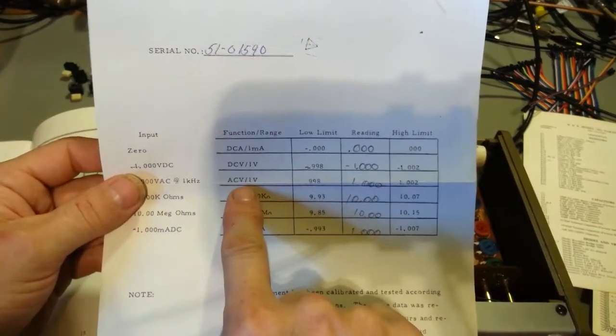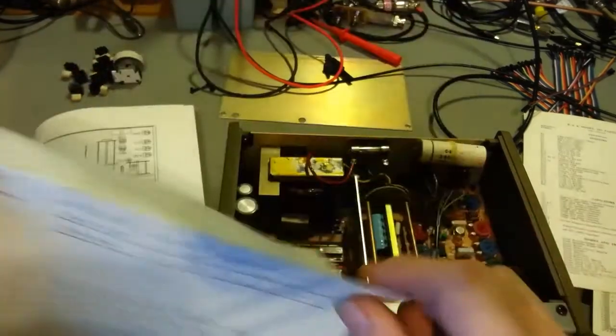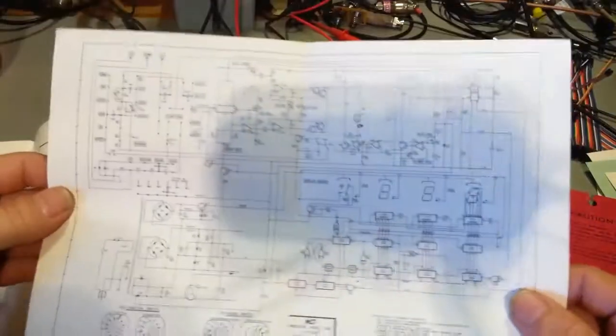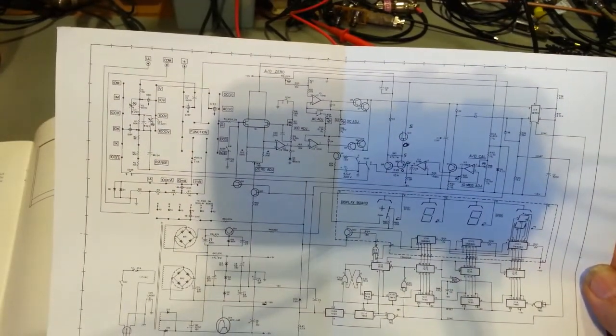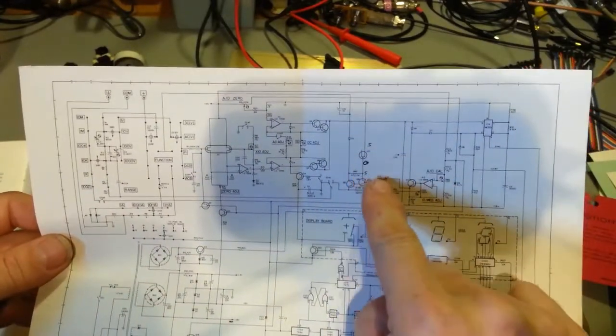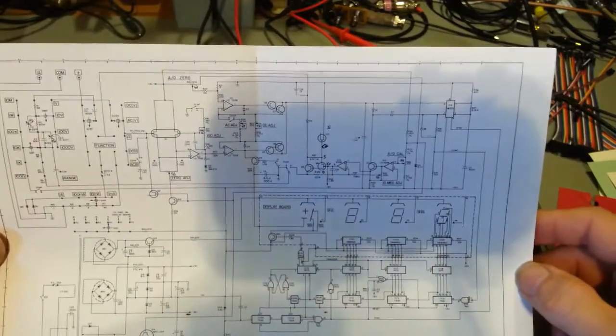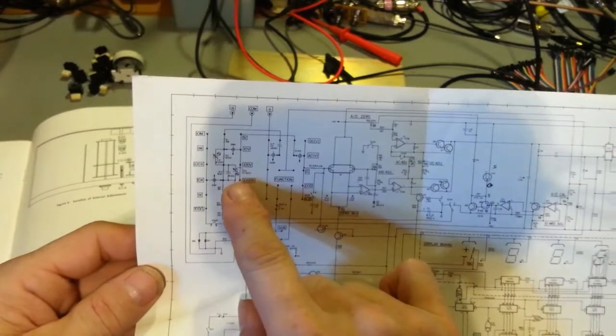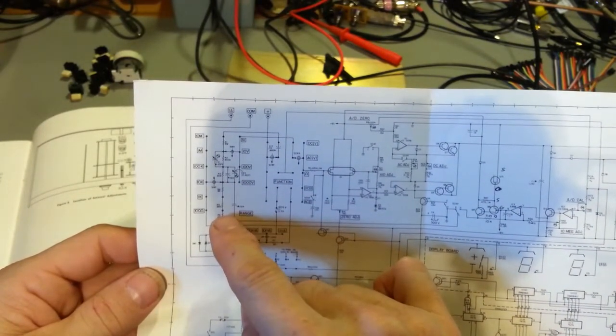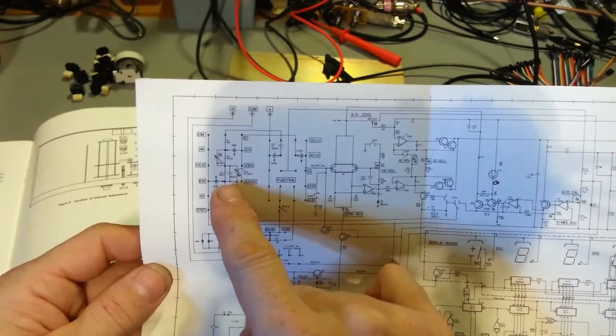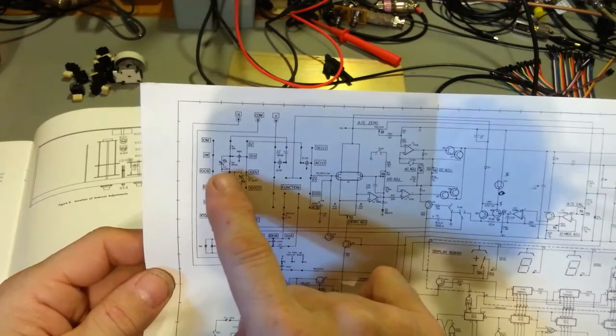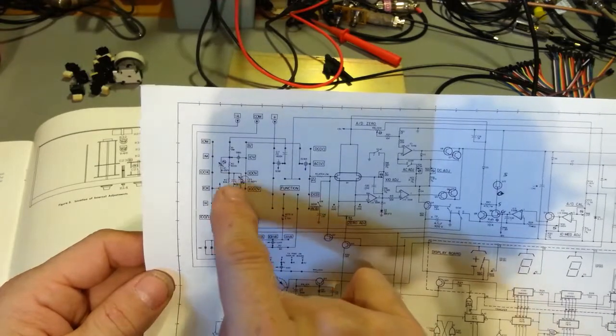Just grab this cal certificate. AC. It's only calibrated at the 1 volt range. Maybe there is a difference in this. I'm not seeing... Looks like somebody's done something to this at some point in time, because they've highlighted the gate and the sources on these FETs here. DC AC adjustment. There don't appear to be... wait a minute, right there. So they show them on the schematic. But okay, this one's in parallel with another fixed capacitor. Now, they're not showing it in parallel with one there, but that would be in series with this other capacitor.